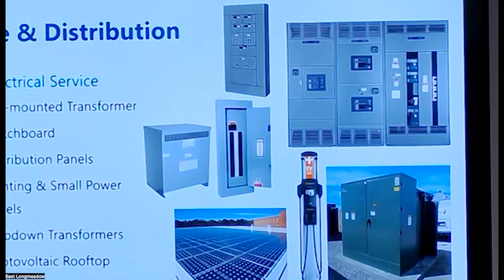Since the HVAC system and a portion of, or maybe all of, the plumbing system is all electric, but especially because of the HVAC, it's a heating system, and we need to provide power to prevent freezing. It's a large power that we need backup. The generator will be a large size, so don't be surprised. We are estimating it at approximately 800 to 900 kW. It will be a diesel-fired generator with a fuel tank for 24 hours.